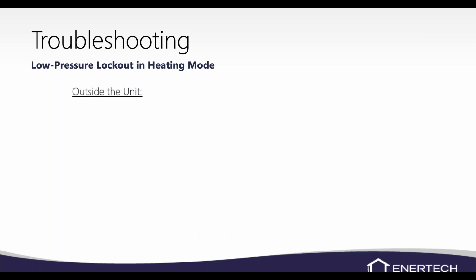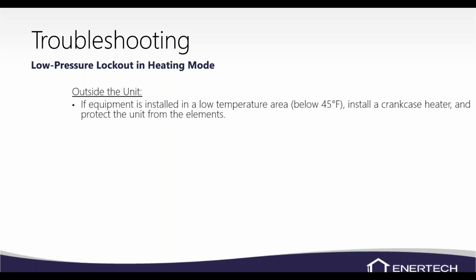Low pressure lockout in heating mode. This would be the source side as well. So we're looking at the loop field or the pump and dump. Outside the unit, if the equipment's installed in a low temperature area, we could have a problem with the compressor wanting to start on a cold startup, and you may want to put a crankcase heater on the unit.